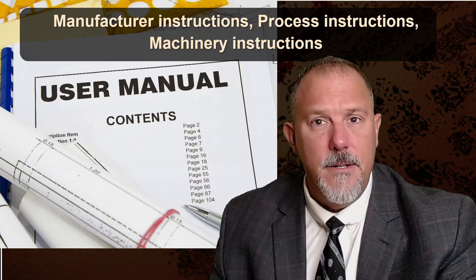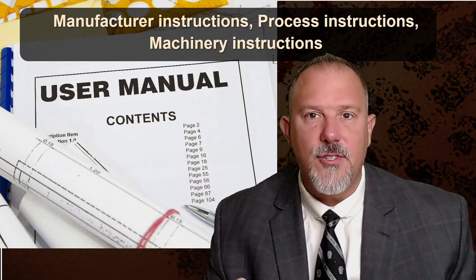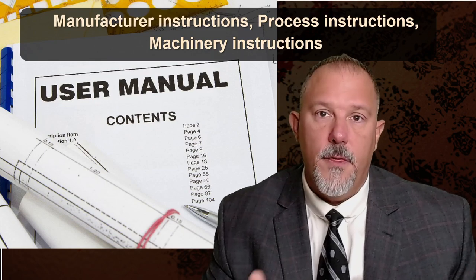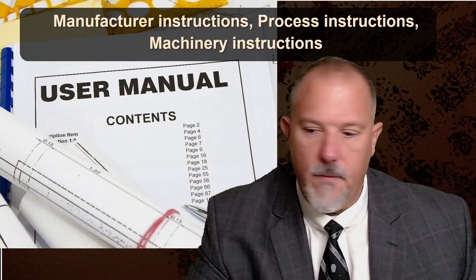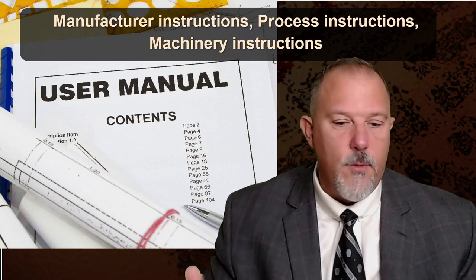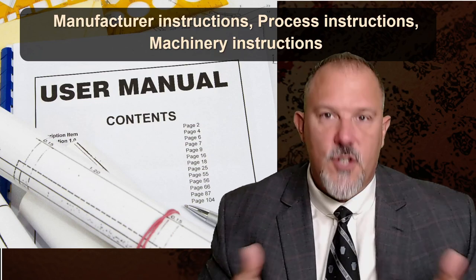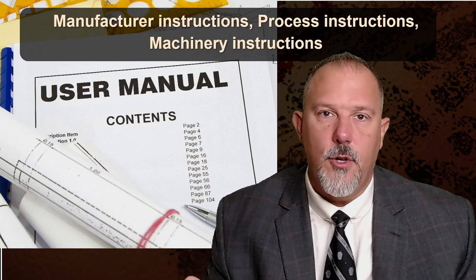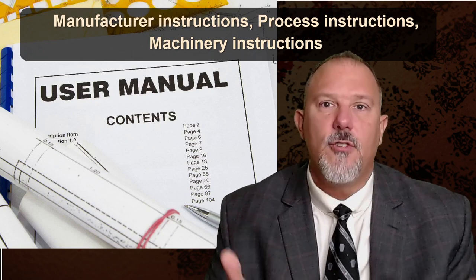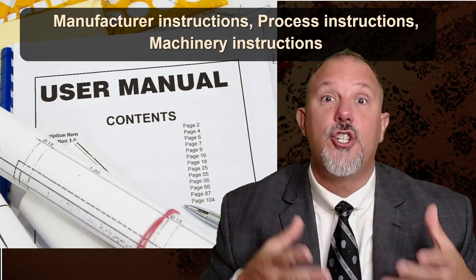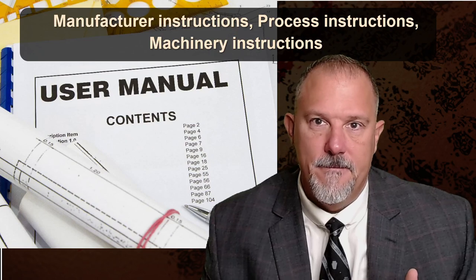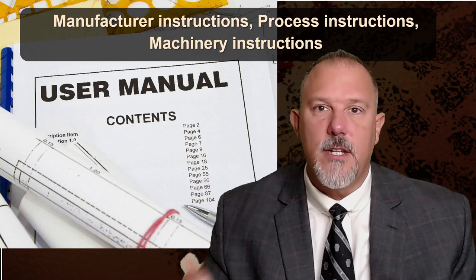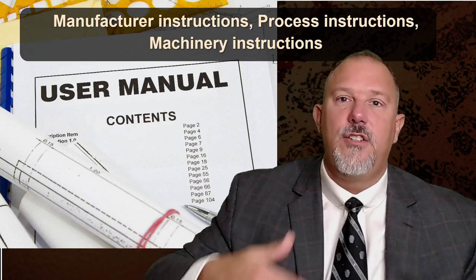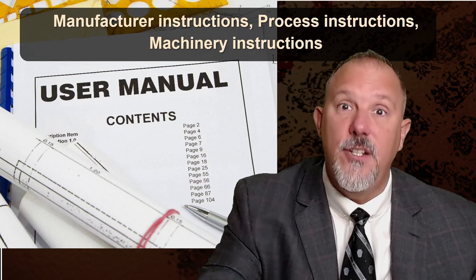Think about that. How can I recognize the hazards if I don't understand the solution? Take a receptacle for perspective. Wish I had one in front of me here. You have terminals on the receptacle. You've got to know what's energized, what is not energized. How do I determine what is energized? If I'm going to establish an electrically safe work condition, I need to verify absence of voltage. How do I do that on a receptacle?